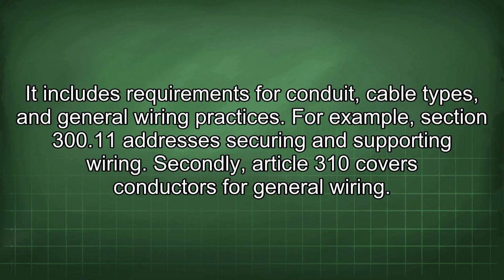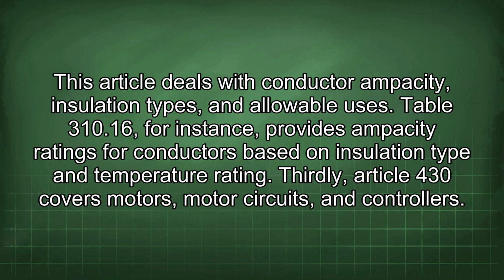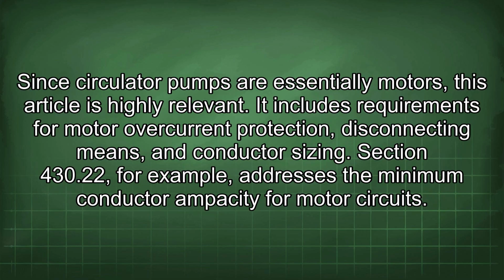Secondly, Article 310 covers conductors for general wiring. This article deals with conductor ampacity, insulation types, and allowable uses. Table 310.16, for instance, provides ampacity ratings for conductors based on insulation type and temperature rating. Thirdly, Article 430 covers motors, motor circuits, and controllers. Since circulator pumps are essentially motors, this article is highly relevant. It includes requirements for motor overcurrent protection, disconnecting means, and conductor sizing. Section 430.22, for example, addresses the minimum conductor ampacity for motor circuits.